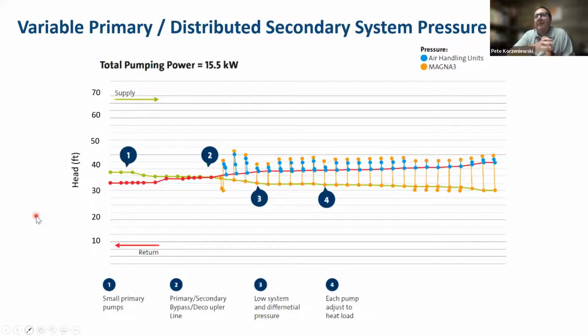If we take a look at that same pressure profile for a distributed pumping layout, it's going to look quite different. The first thing you look at here is that the amount of head required for that primary pump set is very small. In this case, less than 10 feet of head is required, because we're only worried about pumping the mechanical room and the friction loss associated with the pump, chiller, and associated piping.